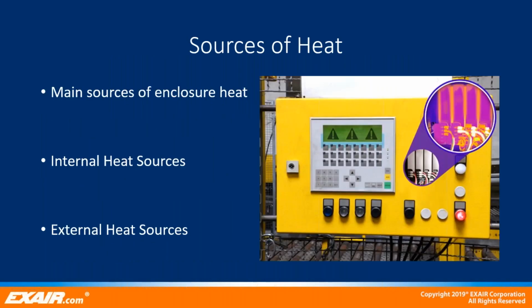Unwanted heat can cause an enclosure's internal temperature to exceed the manufacturer's recommended rating for electrical equipment installed inside. There are two main heat sources that add up to make the total heat load, one being the internal heat sources, such as AC drives, servos, and power supplies. Ironically, the same equipment that can be damaged by heat is creating its very own heat. External heat sources are mainly dictated by the environment in which the enclosure is located.